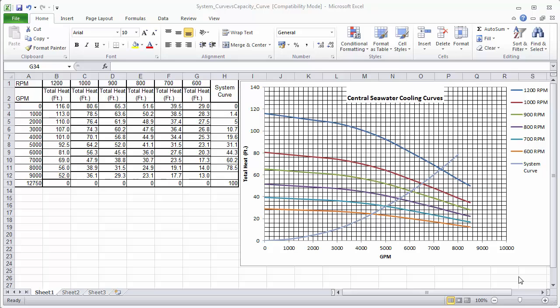The designer quickly noticed the difference between the capacity curve generated by Fluidflow versus that that they had created in their Excel file. We can see in their Excel file that at a speed of 600 RPM the head coordinate starts at 29 feet at 0 gallons per minute and reduces to 13 feet at 9000 gallons per minute.